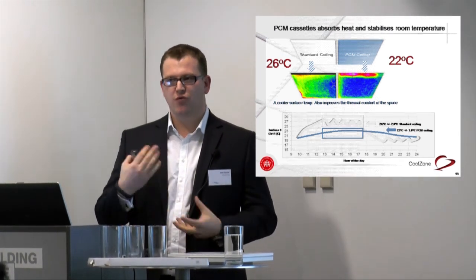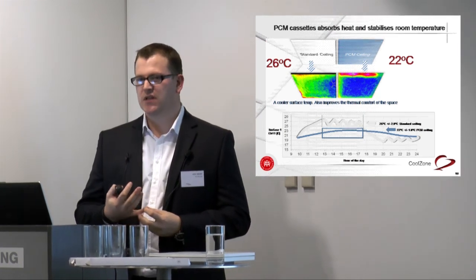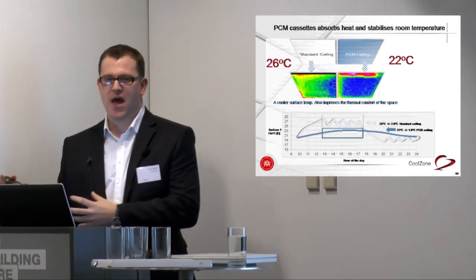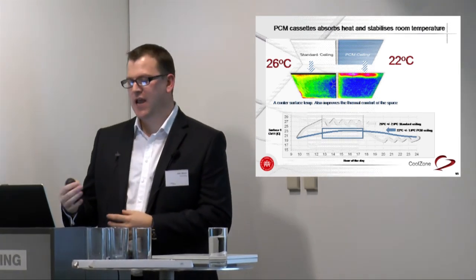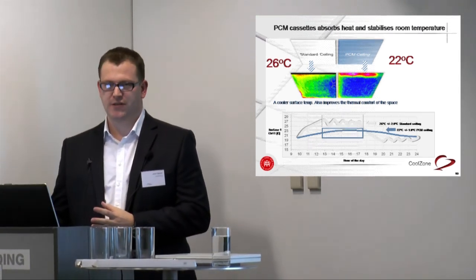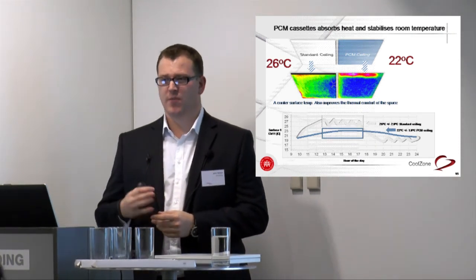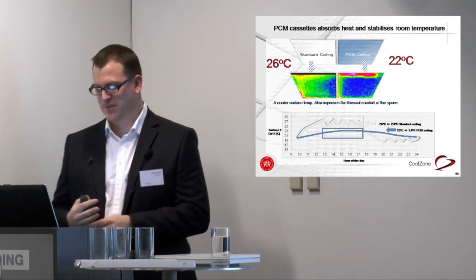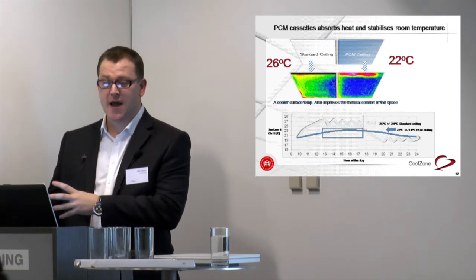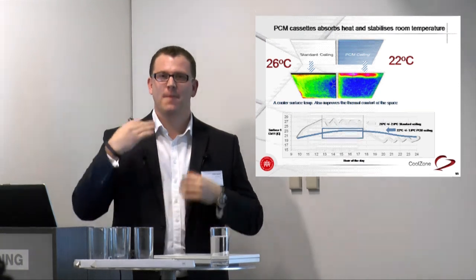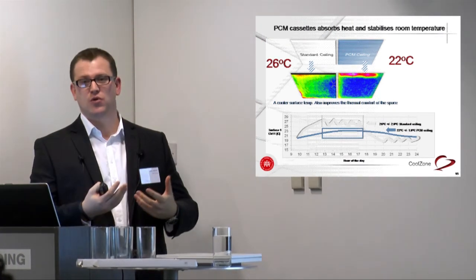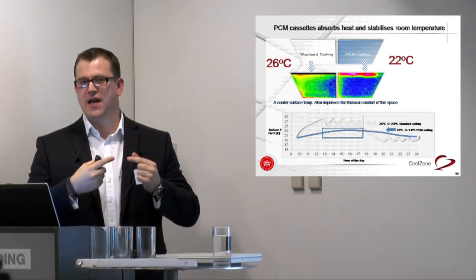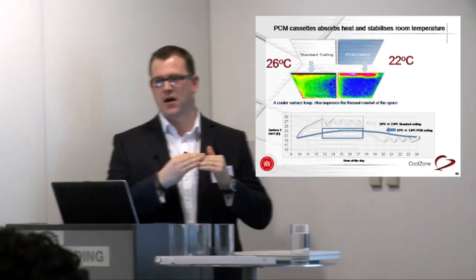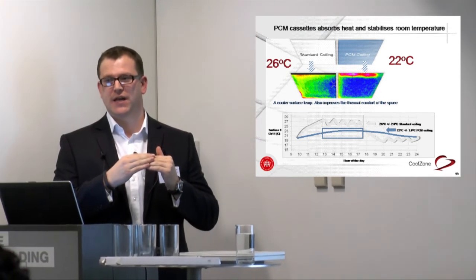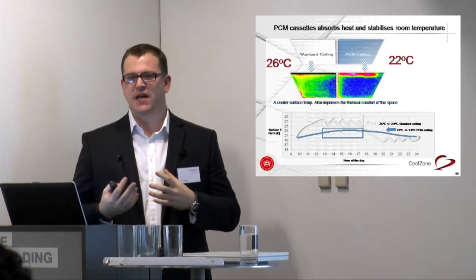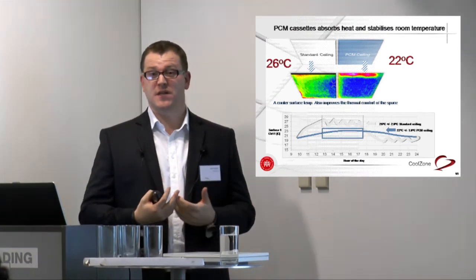Now, I mentioned being able to reset the tiles. The cheapest and the easiest way to do that is to bring in the nighttime air. So typically in the UK we are getting below 20 degrees. Like tonight, I believe it's -2, a little bit later on, maybe not in London. But we can make use of that very cold air, bring it through the ventilation system, pass it over the ceiling, and cool those tiles. So we're able to reset just enough to reset that tile back to square one, back to maximum storage for the next day.